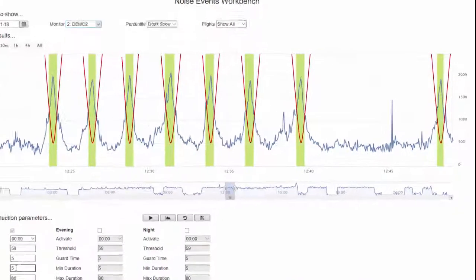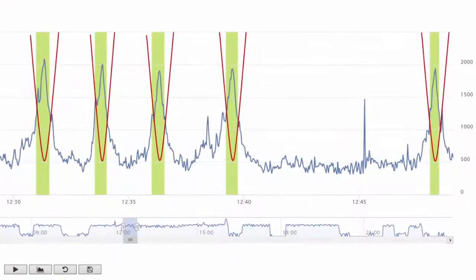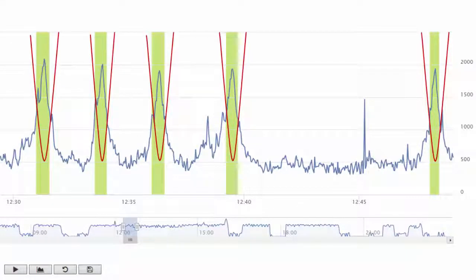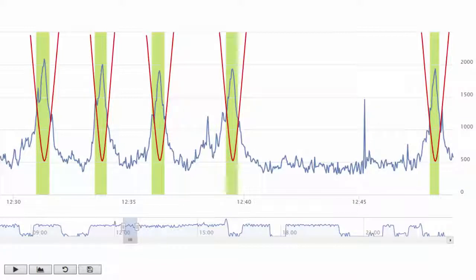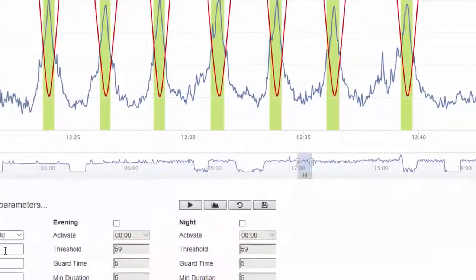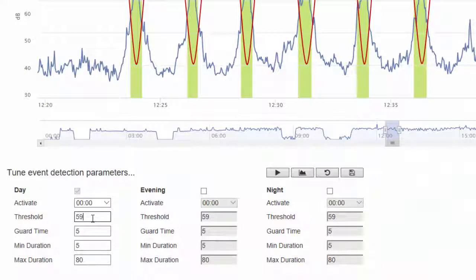There is a single peak that is identifiable as community noise. No aircraft was nearby at the time and the current event detection parameters mean it does not qualify as an event. Specifically it was not above the set threshold for the minimum duration. And here it's 5 seconds.